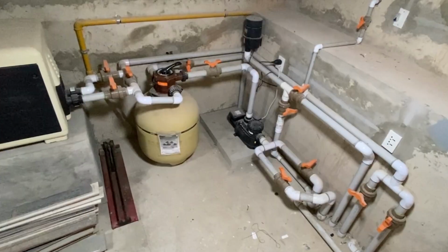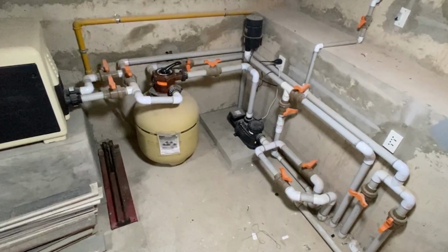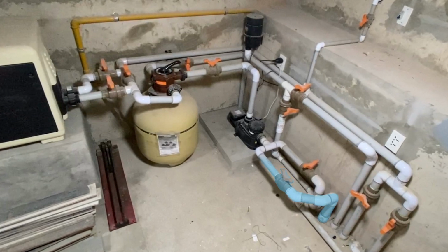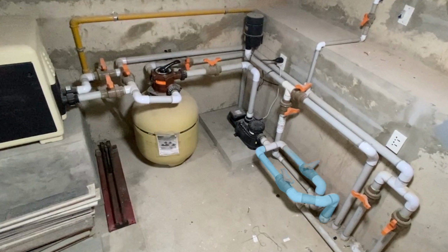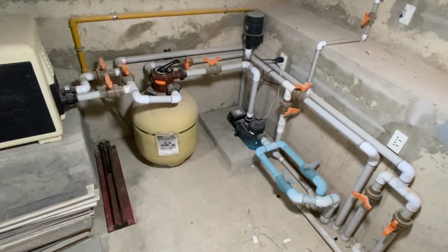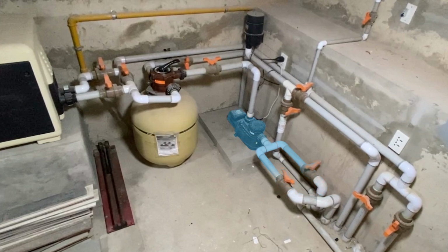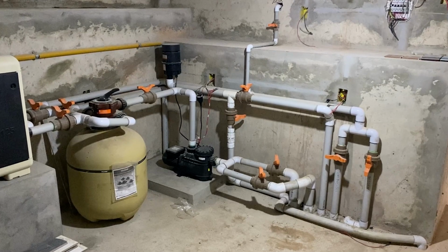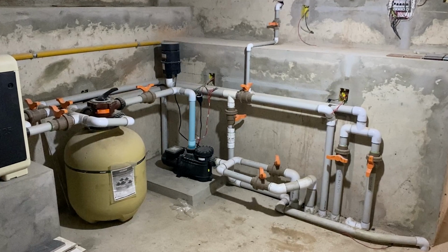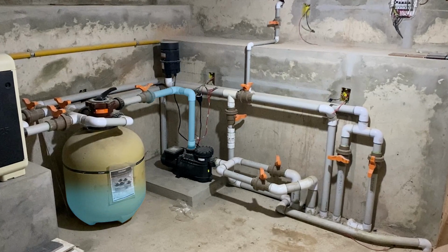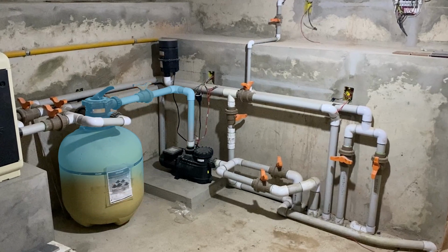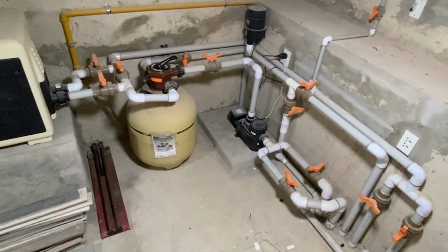First of all, you need to know how to identify which valve corresponds to which accessory. So before the pump are the valves for the bottom drain, also the skimmer, and if you have, also the suction point. These three, or like in this example, there are only two, which are the skimmer and the main drain, enter through the side of the pump, regardless of the brand or type of your pump. After the pump, the water comes out of the upper part towards the filter. In the middle, it is useful to have a valve, especially if your pump has not variable speed. This valve must remain open in all situations.